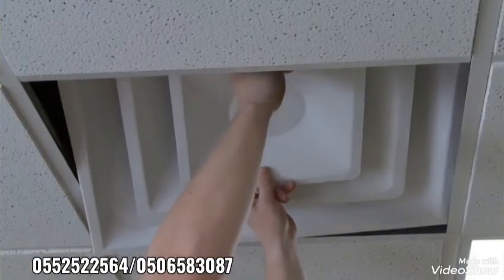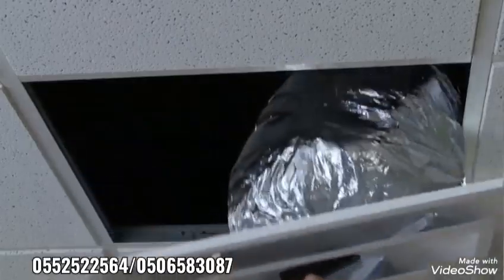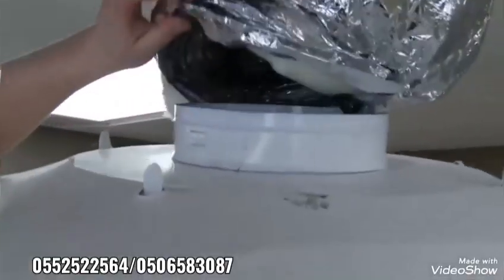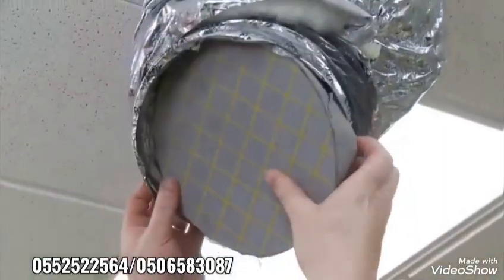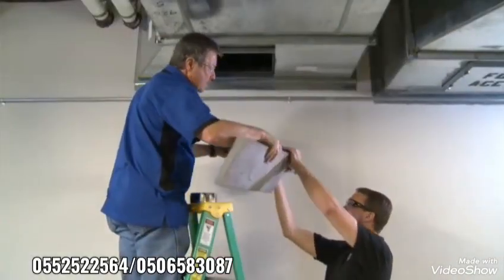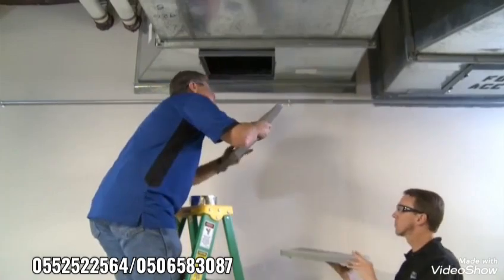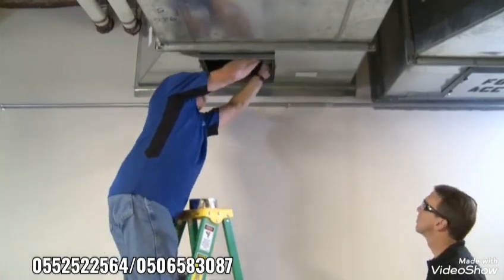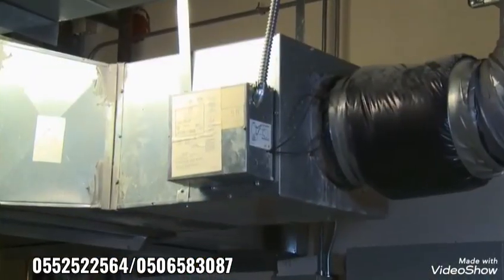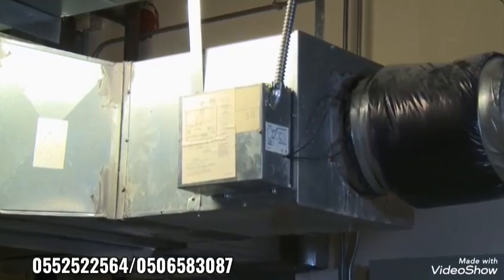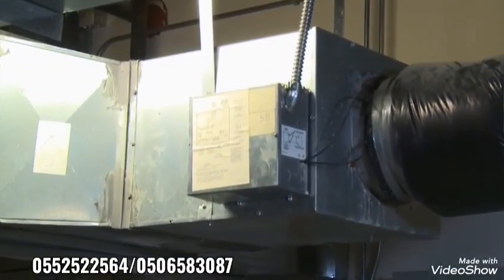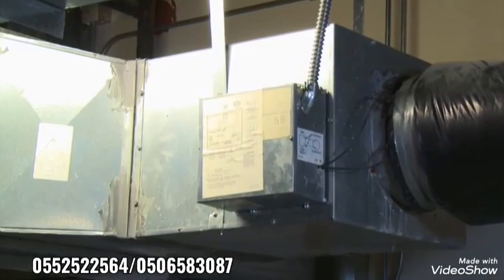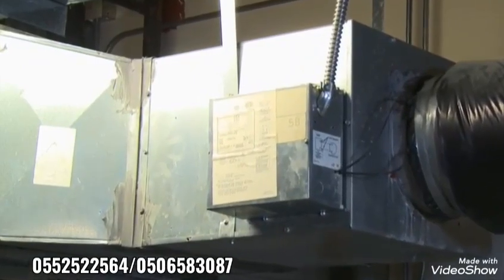For constant volume systems or returns, the diffusers and grills serving that section of ductwork are removed and foam plugs are inserted into the end of the duct to block air from escaping. This effectively isolates the portions of ductwork being sealed. For variable volume systems, blocking material is inserted upstream of the inlet to the terminal box to ensure coils and pressure sensing devices are not exposed to sealant.